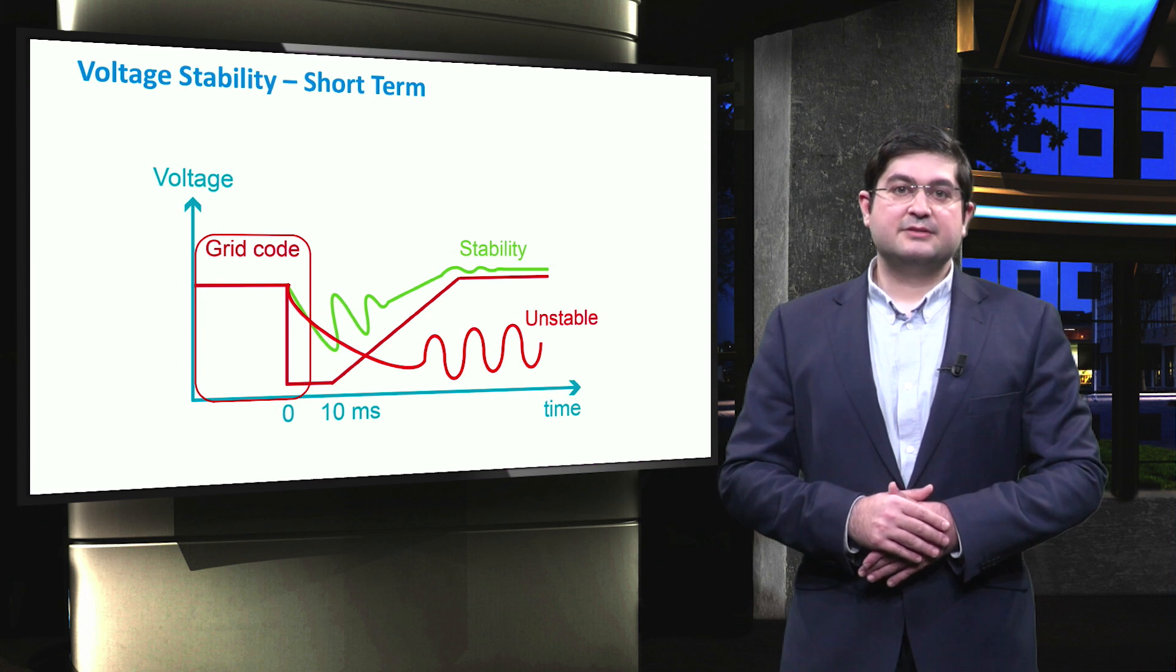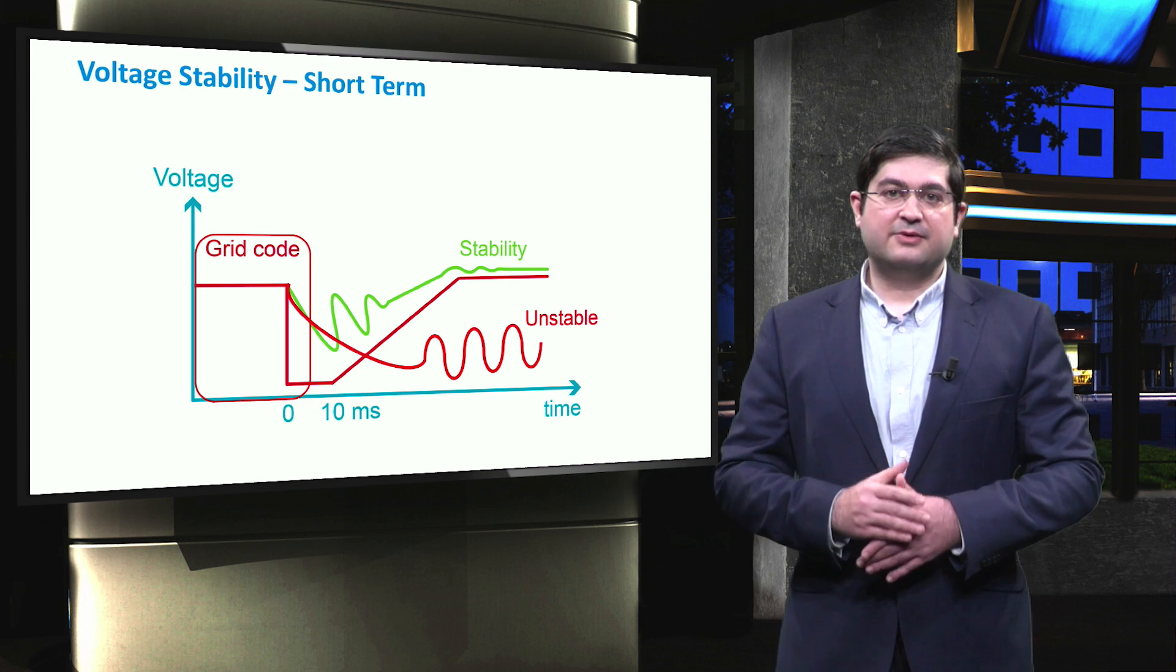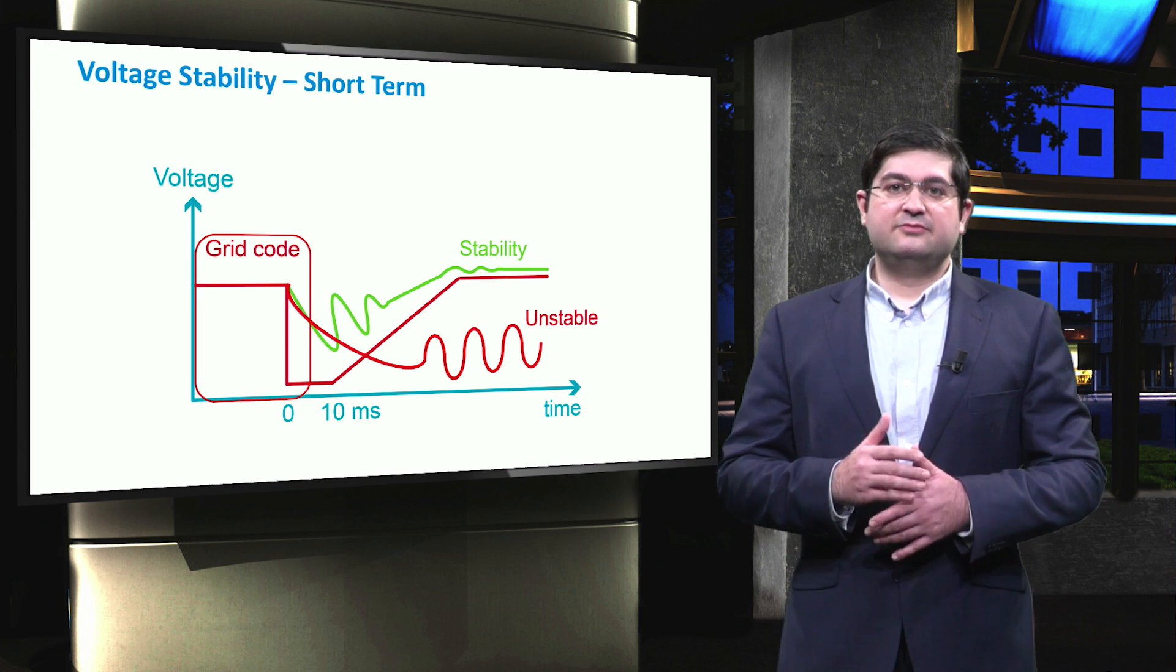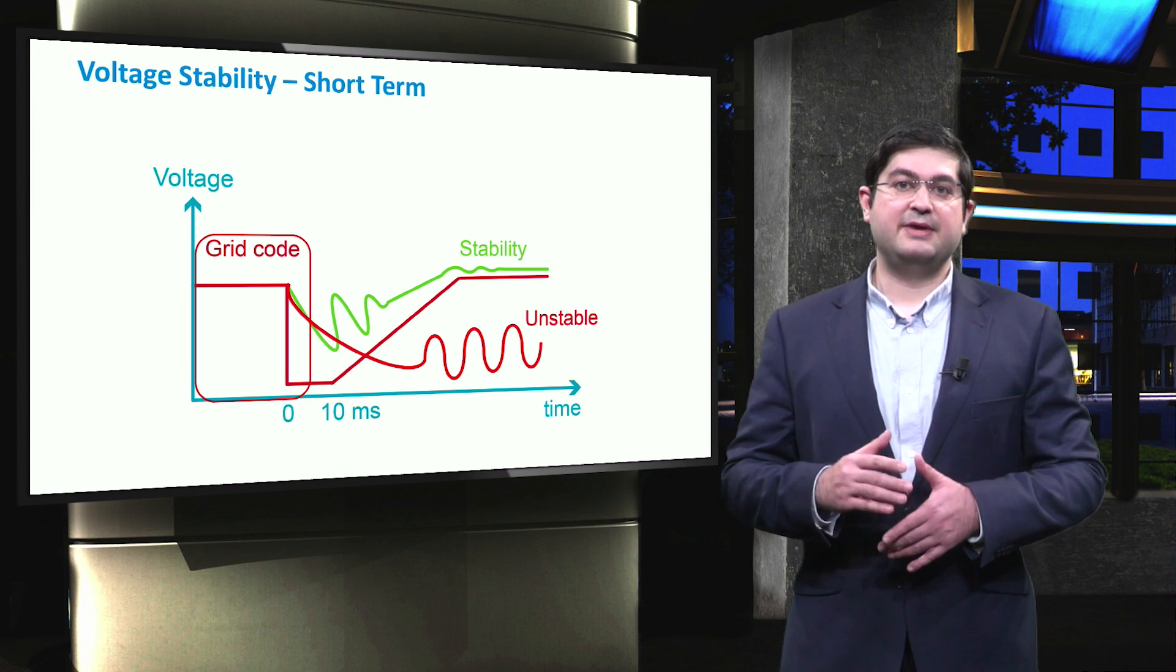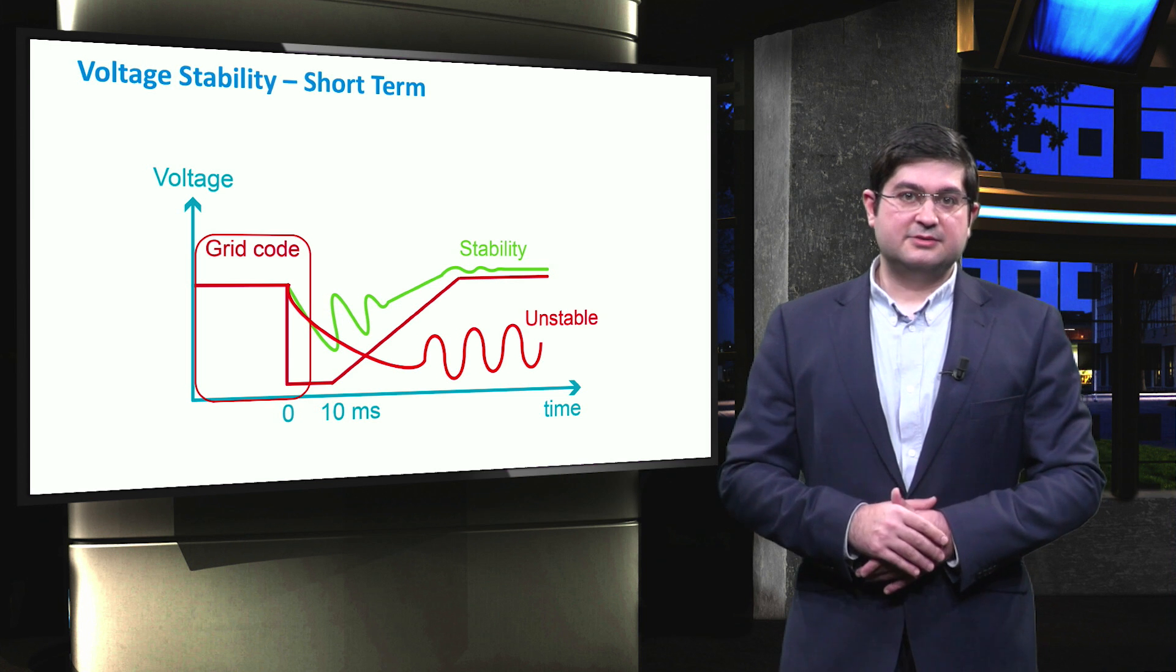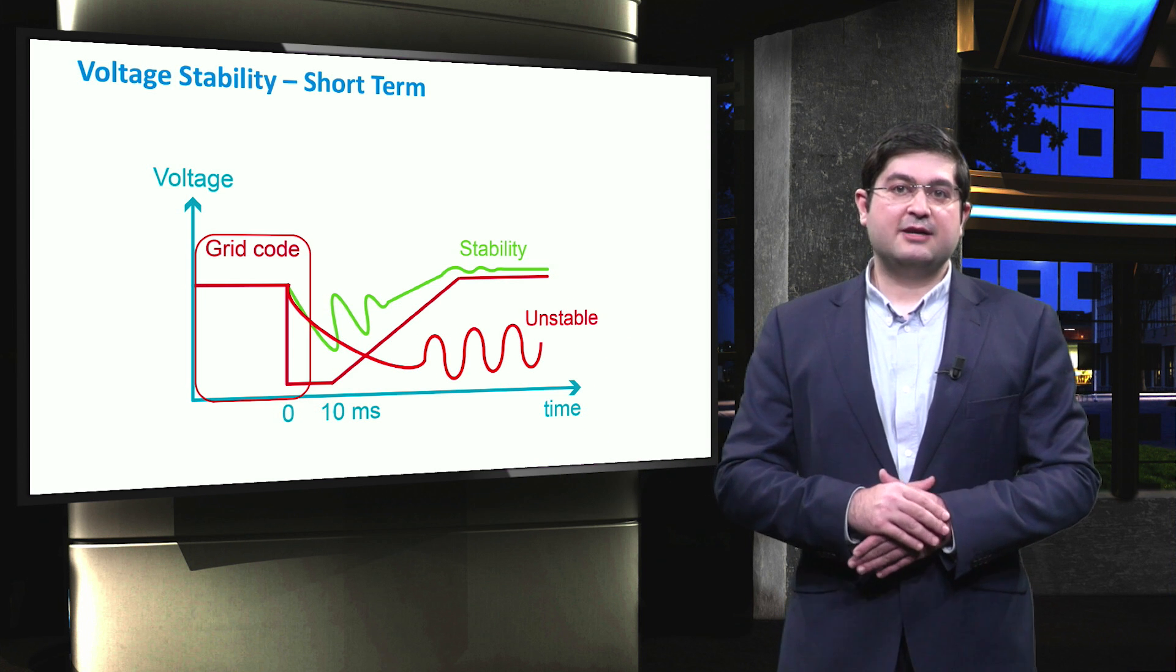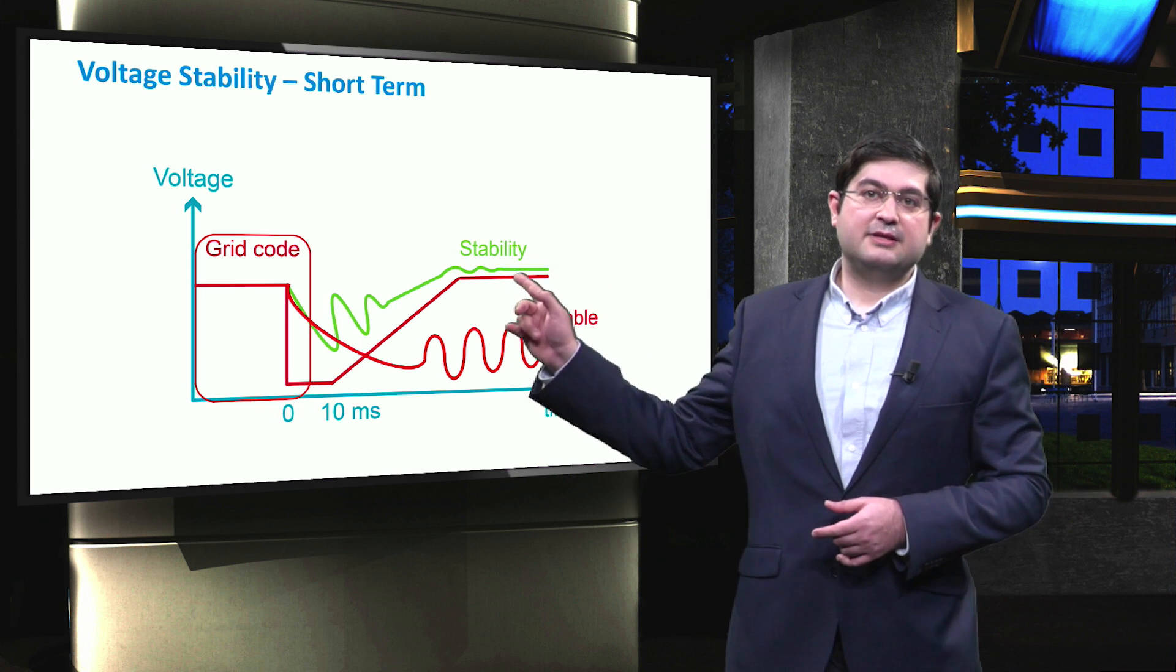If the microgrid is connected to the grid, then transient voltage stability is a relevant problem, particularly during upstream network faults. We remind that transient voltage stability refers to the capability of a system to maintain synchronous operation when they are subject to faults. As it is shown in the figure, there are grid codes with which microgrid shall comply during faults to reach a stable point after the fault.